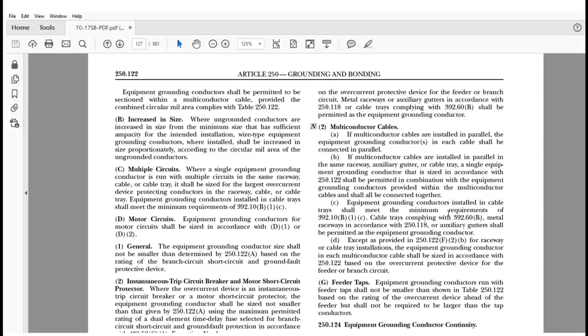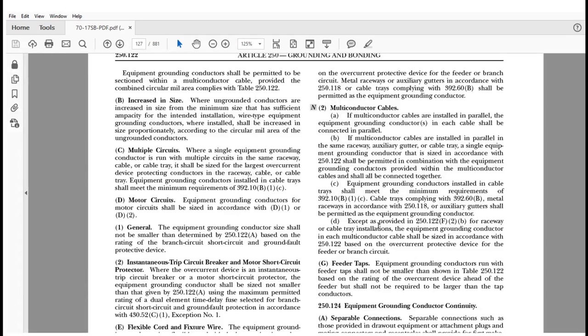But you have to meet the minimum requirements of 392.10(B)(1)(c). Jot that down, go look at it. We don't have the time to go into every aspect of the code because this is just a change class. But you have to understand that it has to meet these minimum requirements. So I encourage you to write that down and go look at it. Now, except as provided in 250.122(F)(2)(b), which is F2B right here, this one.